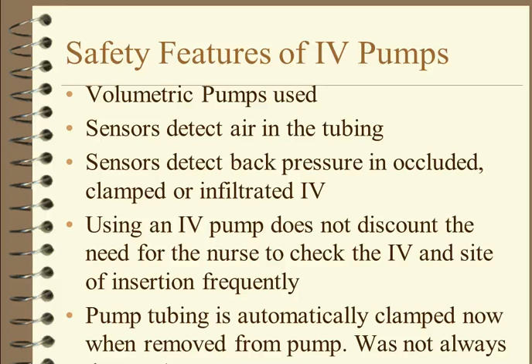It used to happen that if you pulled the tubing out of a pump, it would run free, and so you had to make sure you roller clamped it quickly. Some patients got dangerous medications, such as magnesium, that were added to the IV bag, and that could be very, very dangerous. I'm sure Gail will talk about that, but it was not always true that it used to clamp off. Now the tubing has special safety attachments that clamp the tubing the minute it's pulled off a pump.